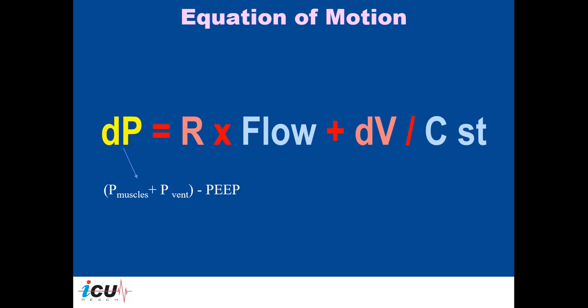In volume control mode of ventilation, the volume is fixed and the machine will use whatever pressure is required to deliver that volume, regardless of resistance, flow, and compliance. If there is any increase in resistance, increase in flow, or decrease in compliance, the pressure applied by the ventilator will be higher, because the aim of the ventilator is to deliver a fixed volume. Therefore, the dependent variable is the pressure — any change in resistance, flow, and compliance will lead to a change in the pressure applied.